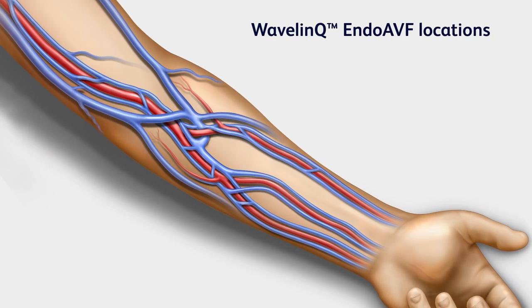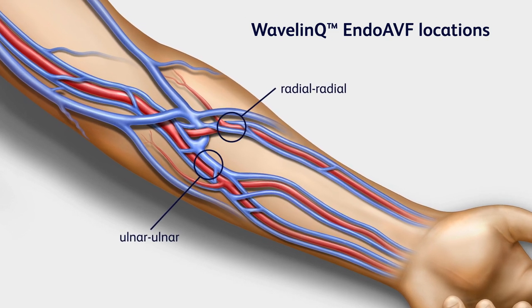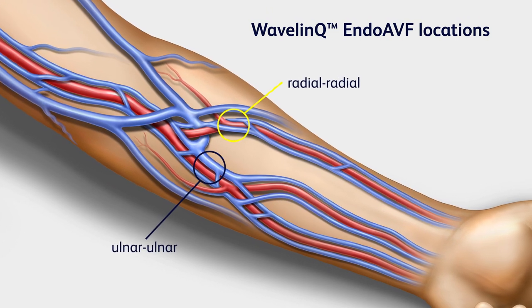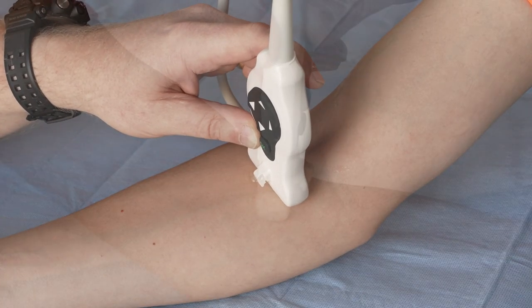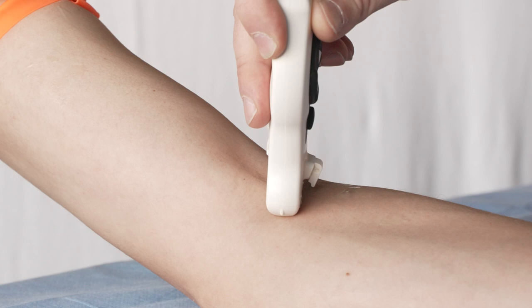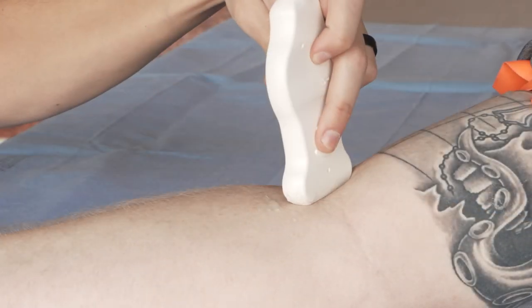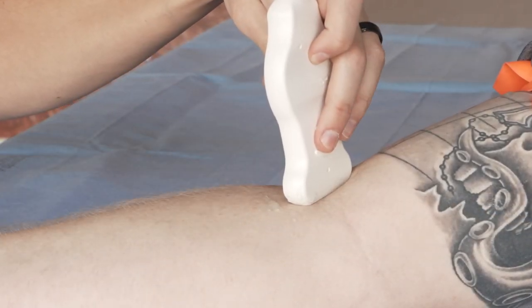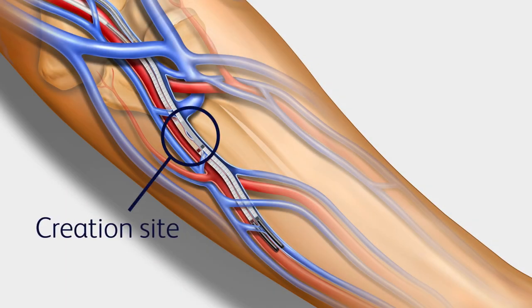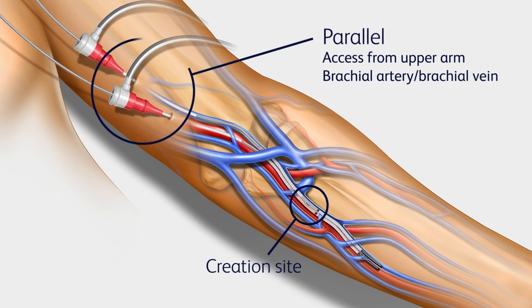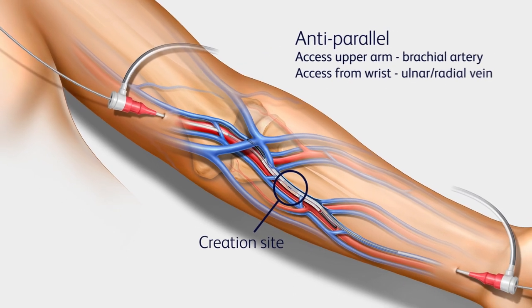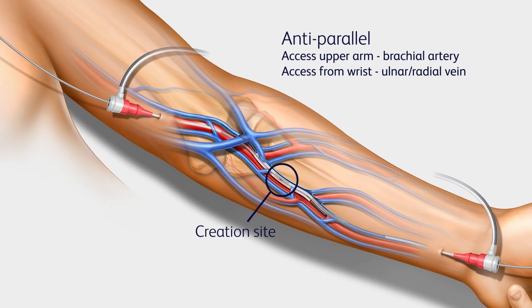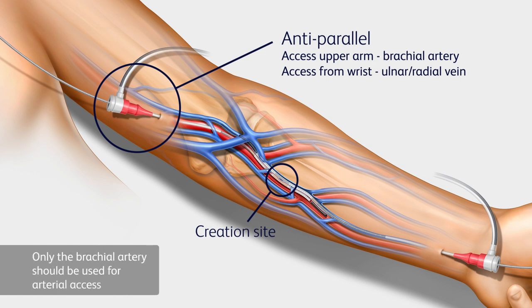Your procedure plan starts with choosing the Endo-AVF creation site, either ulnar or radial. Because human anatomy differs from person to person, your approach to the Endo-AVF creation site will vary, and the WavelinQ Endo-AVF System allows for this. You may choose a parallel approach by accessing the upper arm brachial artery and brachial vein, or an anti-parallel approach by accessing the upper arm brachial artery and the ulnar or radial vein at the wrist.